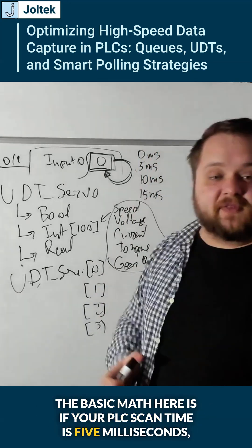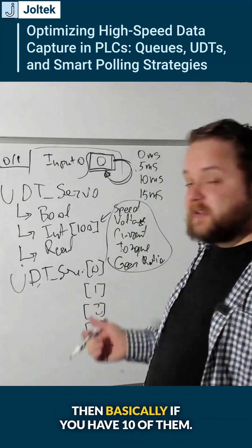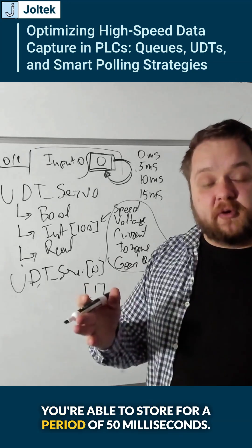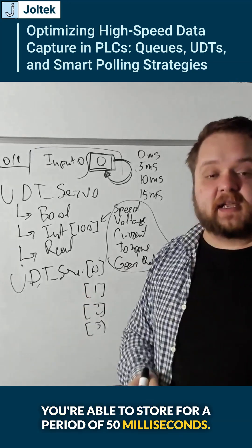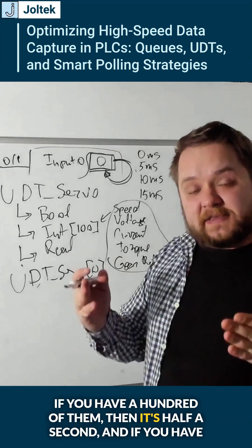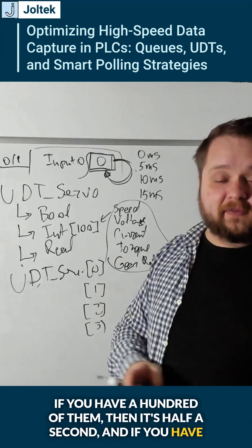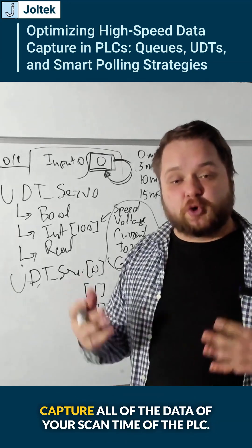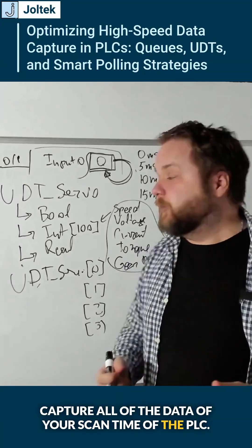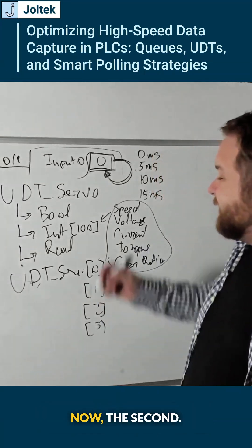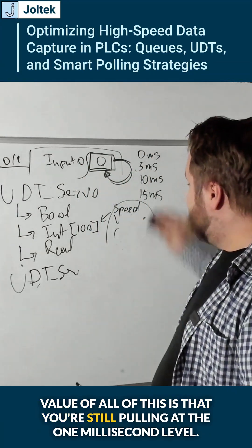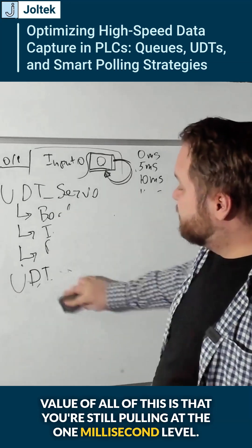The basic math here is: if your PLC scan time is five milliseconds, then if you have 10 of them you're able to store for a period of 50 milliseconds. If you have a hundred of them then it's half a second, and if you have 200 of them then you should be able to capture all of the data within your PLC scan time.